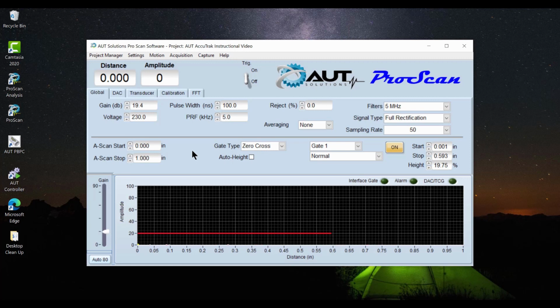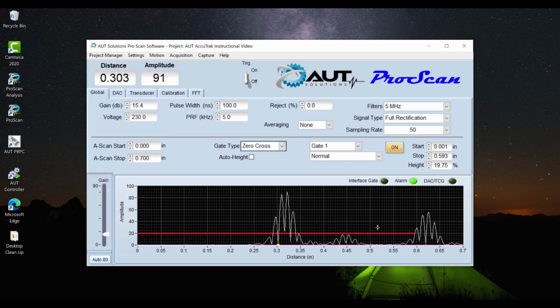We can do some range adjustments here as well. Couple things that we can go over real quick. So you'll notice we have a good screen height. Signal's a little high, so we're going to drop it down to 80%. Alright, our screen range is a little bit longer than what we need to, depending on what your procedure says. Some require 2 back walls. If that was the case, I would simply come in here, change it to 0.7. Now you have your 2 back walls displayed. However, we don't need that right now.